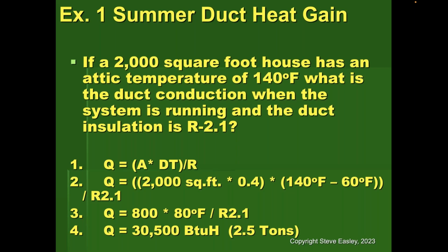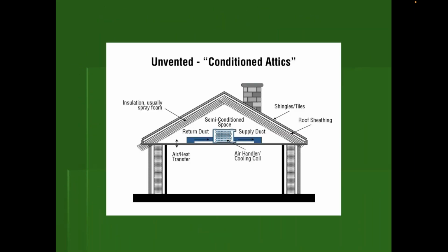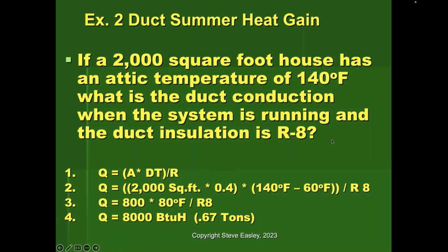So we did some basic math here, and let's just say we've got a 2,000 square foot house and an attic temperature of 140 degrees, and our ductwork is insulated to R2.1. That's an older home, a home that has old ductwork in it. So that ends up being a total load on that ductwork of 2.5 tons. That means if I've got a 4-ton system, 2.5 tons is just to offset the heat gain in the attic. So that kind of gives you an idea of just how ugly attics are in terms of contributing to the overall comfort and cooling load of a system. Now, if we take this and say, let's go to R8 ductwork, which is required today, that ends up being about 0.67 tons. So it's still almost three-quarters of a ton of air conditioning just from that additional heat gain.